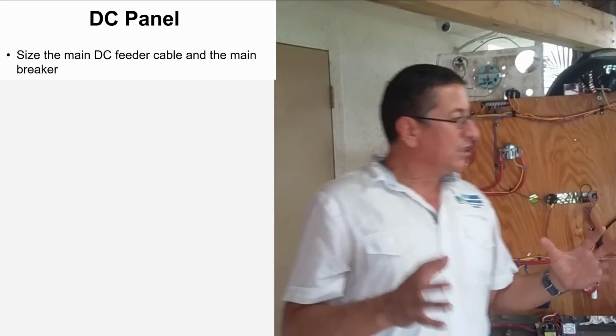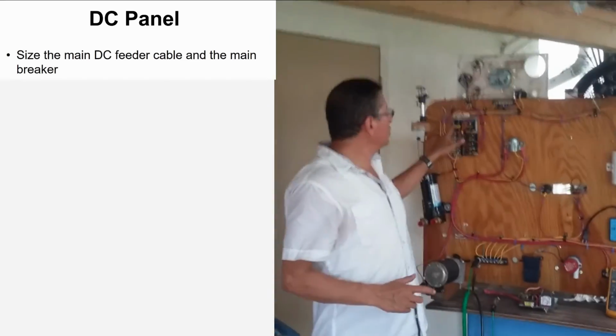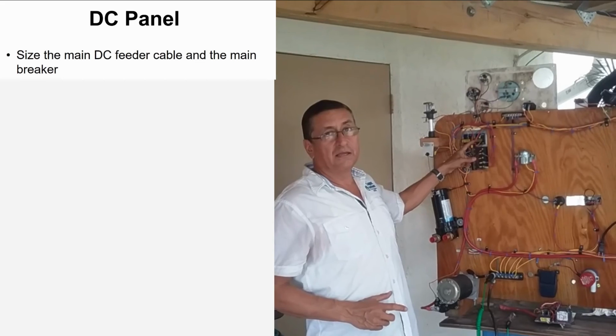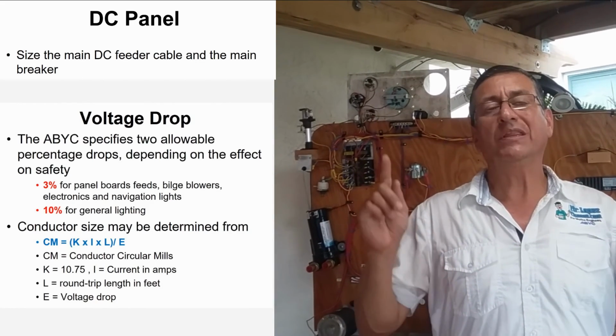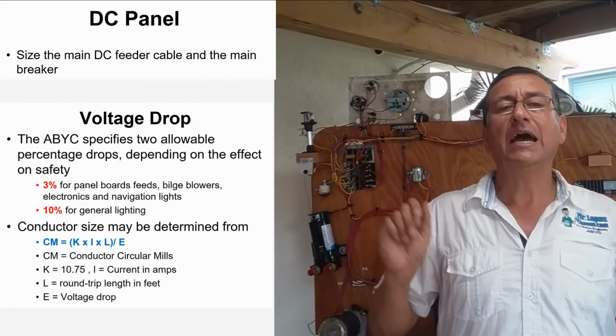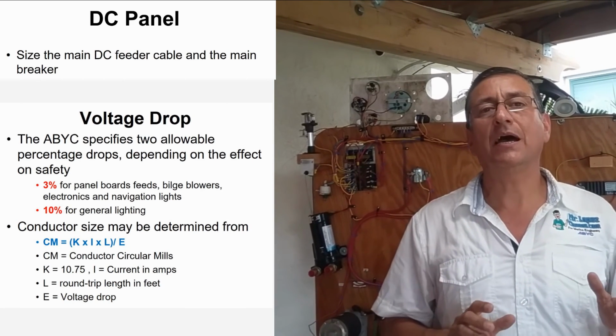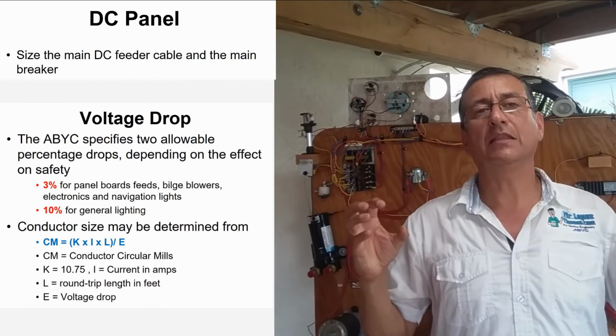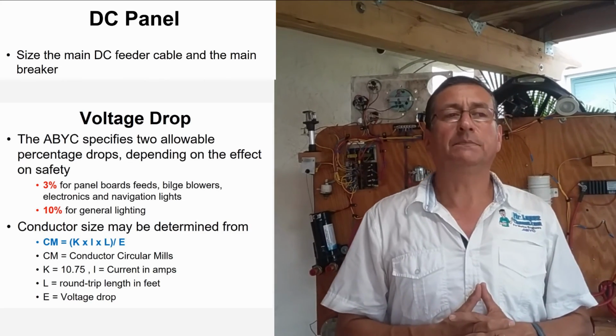In this step, you need to calculate the gauge of this wire. The wire gauge depends on the total consumption in amps and the total distance between the panel and the battery bank.